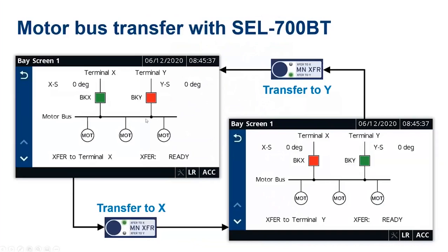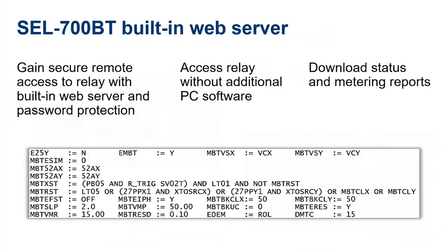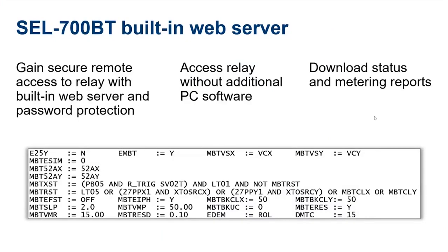So if the Y breaker is closed, then the relay arms itself to transfer to the X feeder. If you push the push button, then it will do the transfer. And it takes 5 seconds to arm the transfer to the other feeder, and that depends on the 52A states. And then you can keep going back and forth between the two systems. And yeah, I think this concludes this part of the presentation. We're going to continue with the settings, and that's all I have for this part of the presentation. Thank you, Marcos.